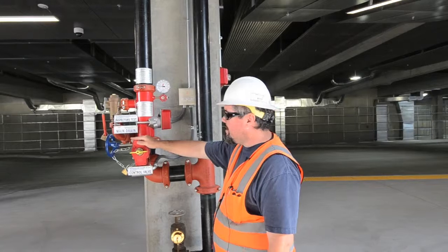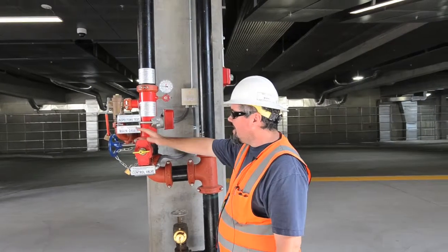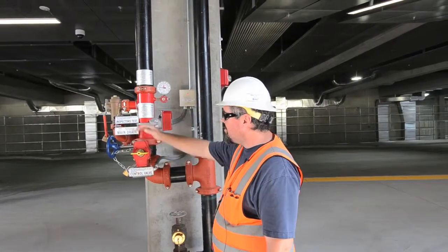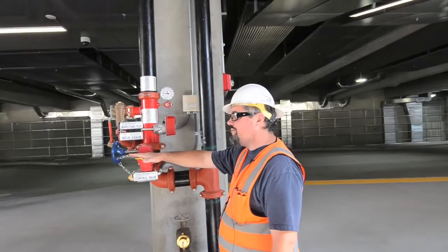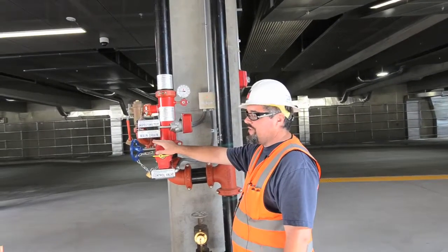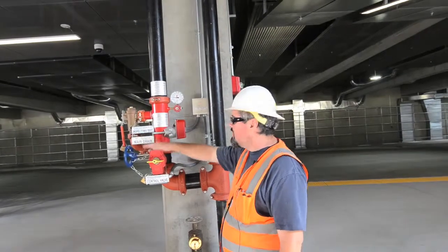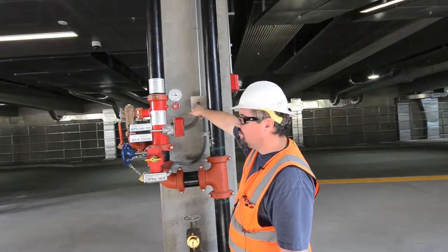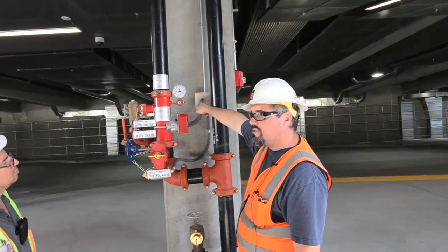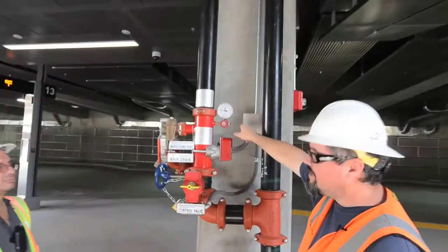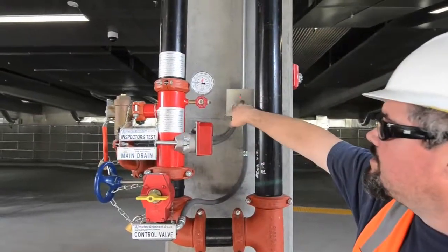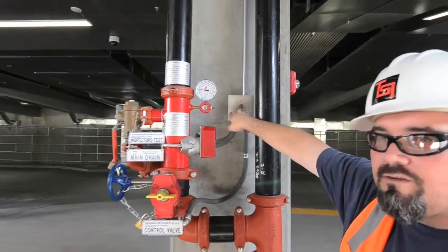And then this tamper right here is to turn the water supply off and on. Right now the Simplex crew turned off their tamper, so we do have troubles in our panel because they had their tampers off. I think they're finished. When we're done, we're going to have to open this up. The monitor module here will go green. Right now it's red because it is closed. I think they're done, but they didn't turn it on, so I'll turn it on for them, and then that should clear and be a green blinking light.